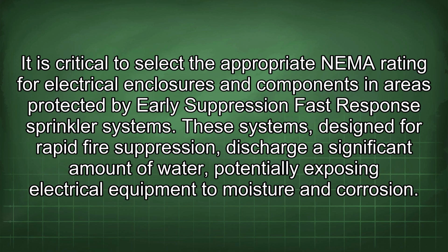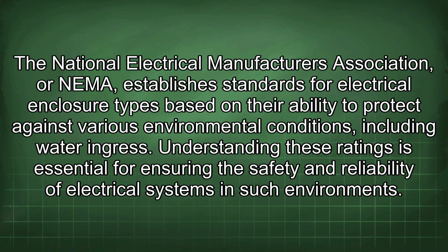It is critical to select the appropriate NEMA rating for electrical enclosures and components in areas protected by early suppression fast response sprinkler systems. These systems, designed for rapid fire suppression, discharge a significant amount of water, potentially exposing electrical equipment to moisture and corrosion. The National Electrical Manufacturers Association, or NEMA, establishes standards for electrical enclosure types based on their ability to protect against various environmental conditions, including water ingress. Understanding these ratings is essential for ensuring the safety and reliability of electrical systems in such environments.